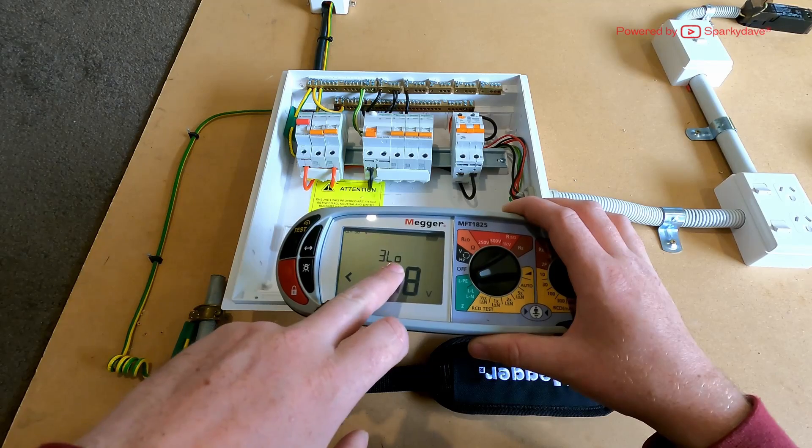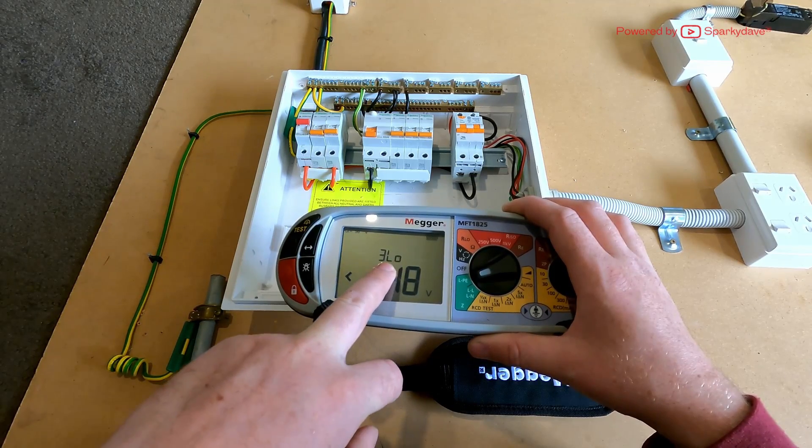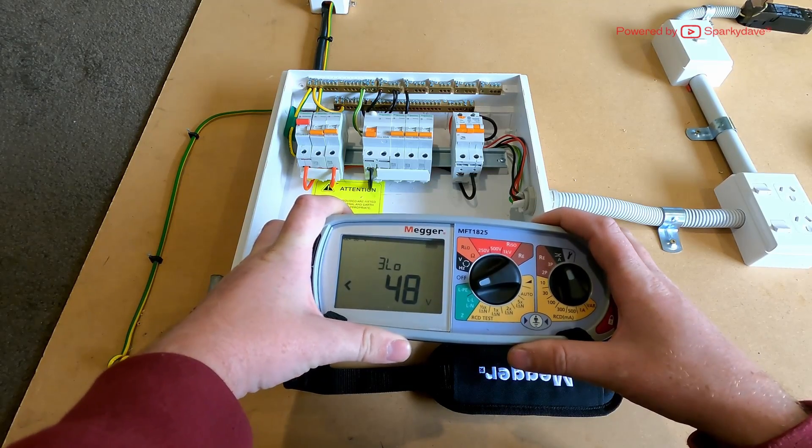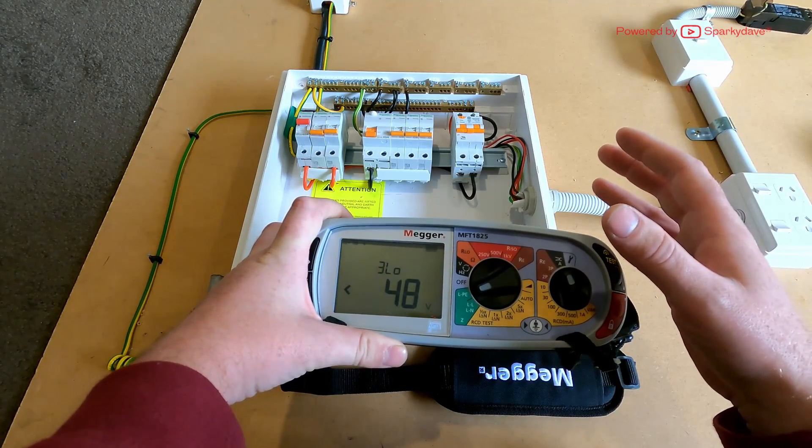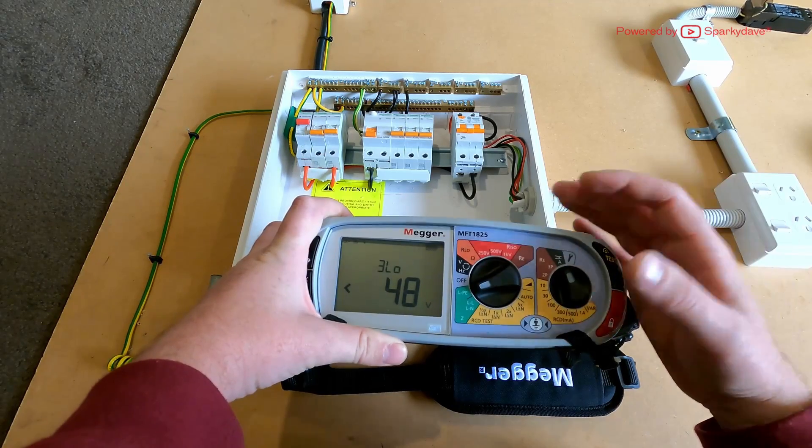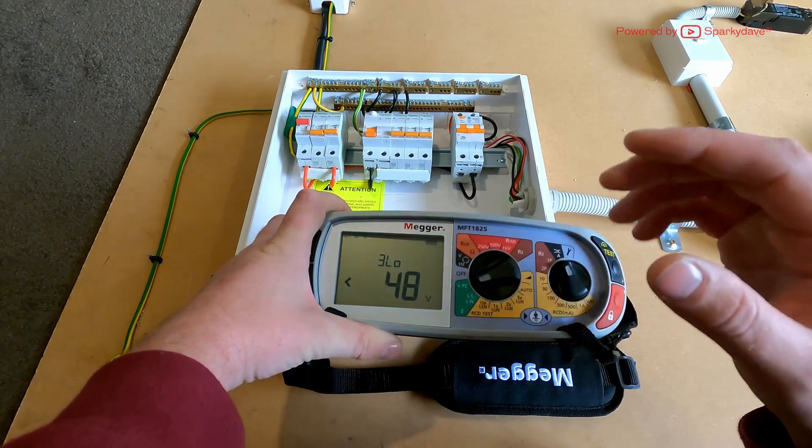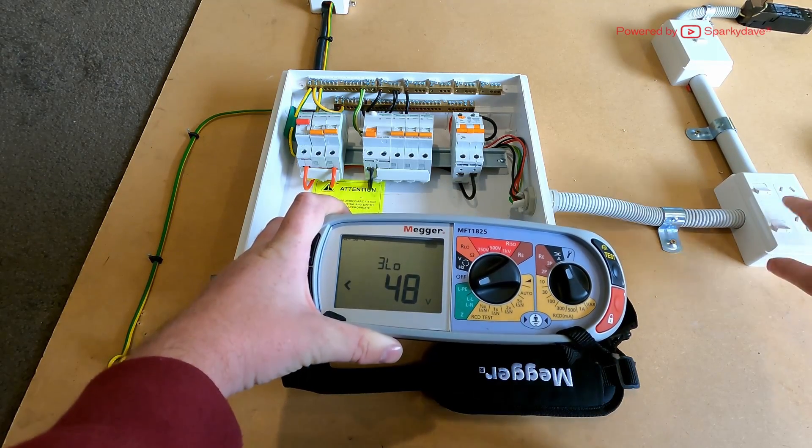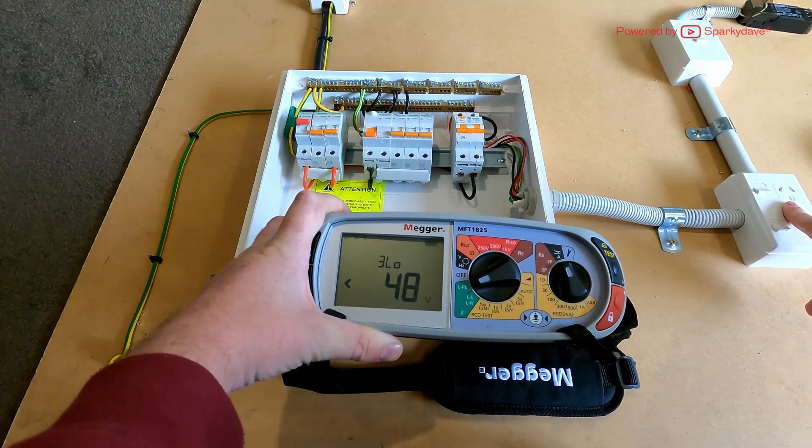By default it comes up with our three lead low current test. That's what the 3LO stands for. Now this test is specifically designed not to trip your RCDs, or to give you the best chance not to trip them. It's never guaranteed, so you'd use this test on the load side of your RCD circuit, so on your socket circuits.